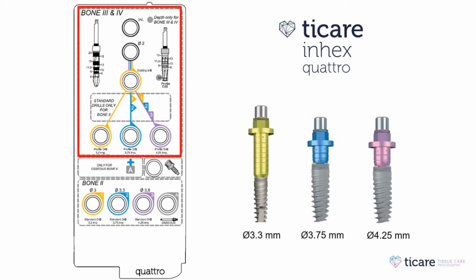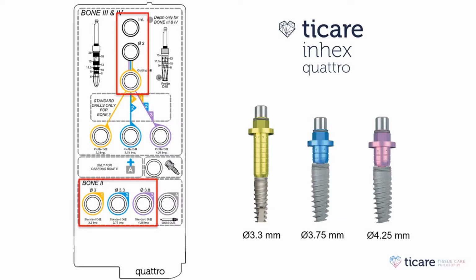These drills will be used when bone type 3 or 4 is available. And adding these other drills, you will be able to place an Inhex Quattro implant in bone type 2. We recommend to use these drills between 800 and 1000 RPM, and these Quattro profile drills will be used at 150 to 300 RPM in soft bone or 800 to 1000 RPM if dense bone is available.